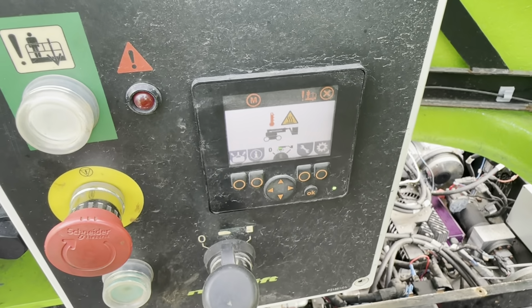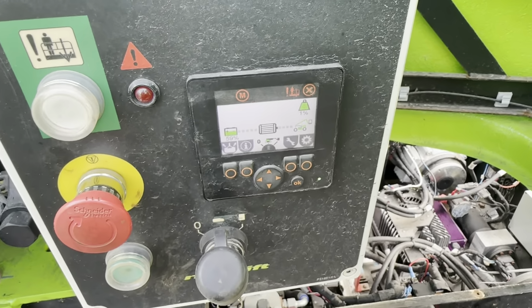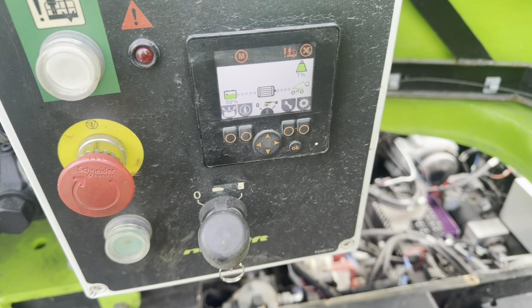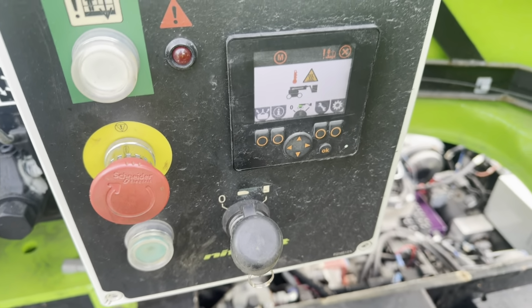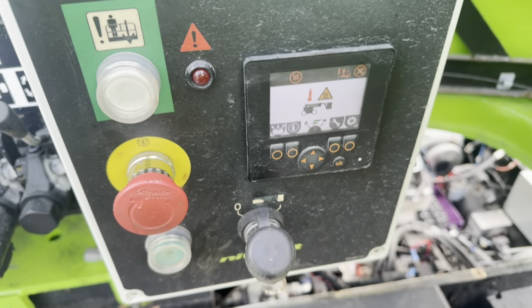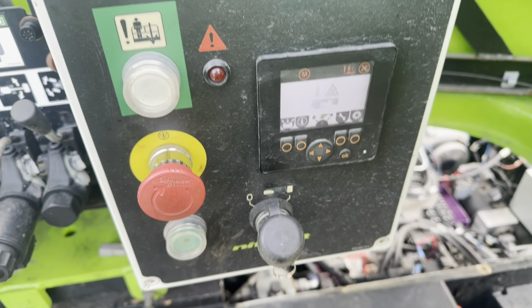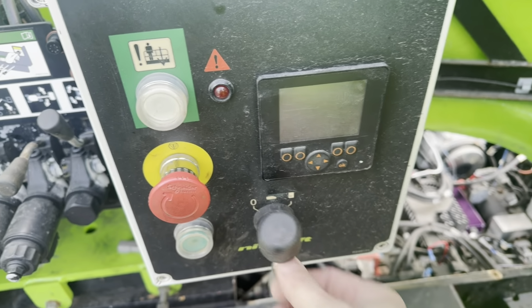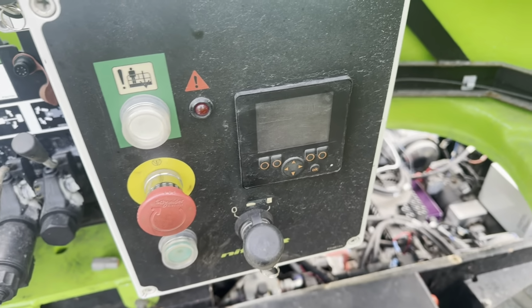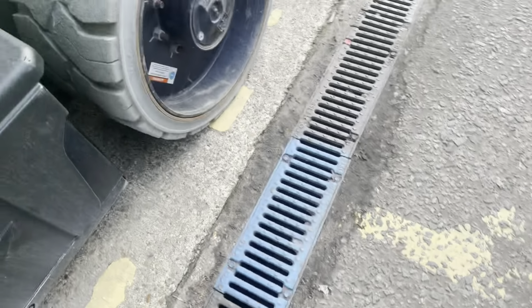That says motor temperature on the master drive controller, so it's saying the master motor is overheating. I've done some checks on it. A few things I've done is I checked the resistance, and I'll show you now.